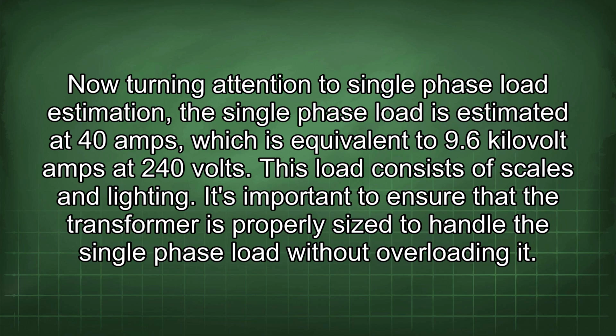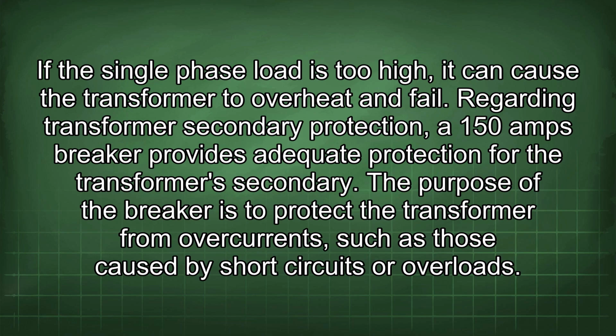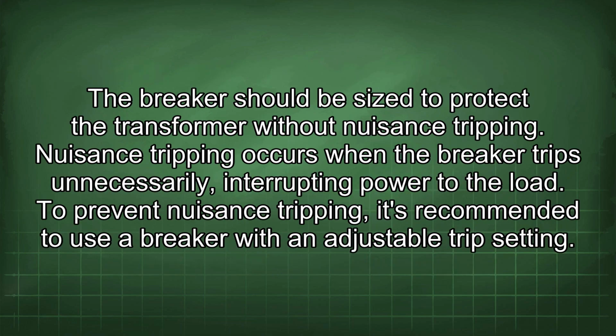This load consists of scales and lighting. It's important to ensure that the transformer is properly sized to handle the single-phase load without overloading it. If the single-phase load is too high, it can cause the transformer to overheat and fail. Regarding transformer secondary protection, a 150 amps breaker provides adequate protection for the transformer secondary. The purpose of the breaker is to protect the transformer from overcurrents such as those caused by short circuits or overloads. The breaker should be sized to protect the transformer without nuisance tripping. Nuisance tripping occurs when the breaker trips unnecessarily, interrupting power to the load. To prevent nuisance tripping, it's recommended to use a breaker with an adjustable trip setting.